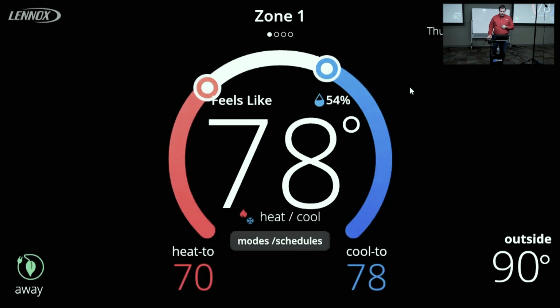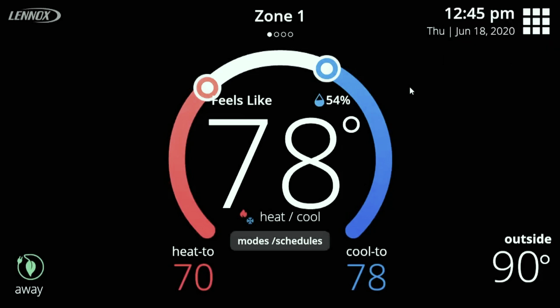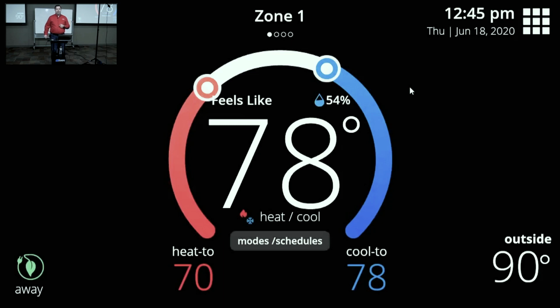So that's what our main screen is going to look like. One of the critical things that I'll tell you guys to pay attention to are these 4 dots here at the top. That can be a very quick indication of whether zoning's functional or not. Because if you have a zone system and you don't have those dots, we're not in zone mode. So a lot of times that either means the discharge air sensor is not installed, or we're having communication problems with one of those zone sensors, and it will eliminate zone mode. So just a quick check there. If you see those dots, then we know you've got communication with all of your components there.